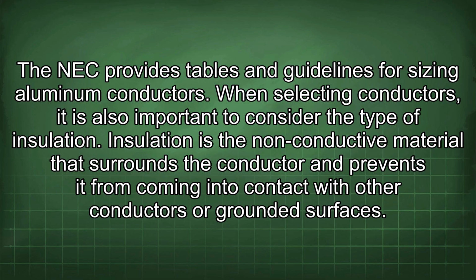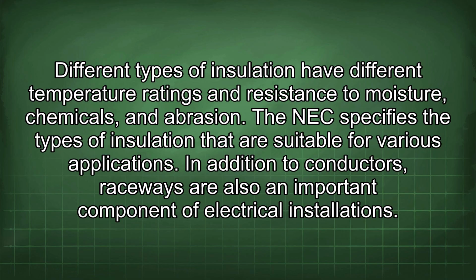When selecting conductors, it is also important to consider the type of insulation. Insulation is the non-conductive material that surrounds the conductor and prevents it from coming into contact with other conductors or grounded surfaces. Different types of insulation have different temperature ratings and resistance to moisture, chemicals, and abrasion. The NEC specifies the types of insulation that are suitable for various applications.